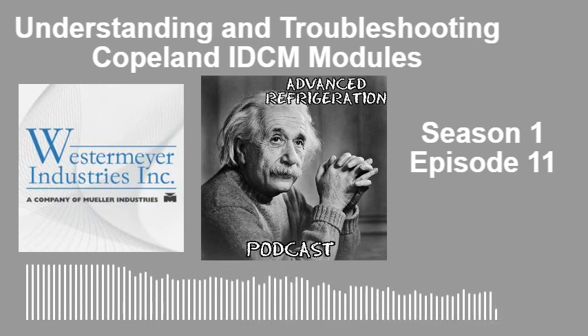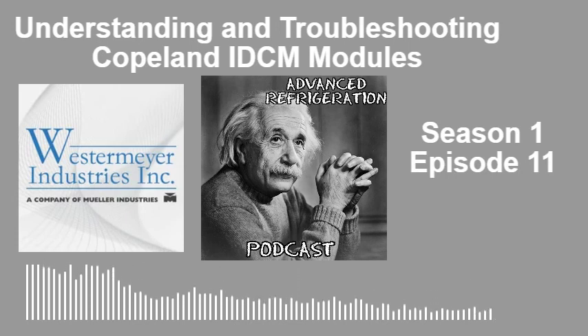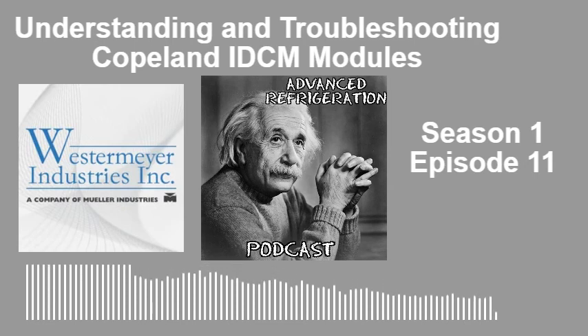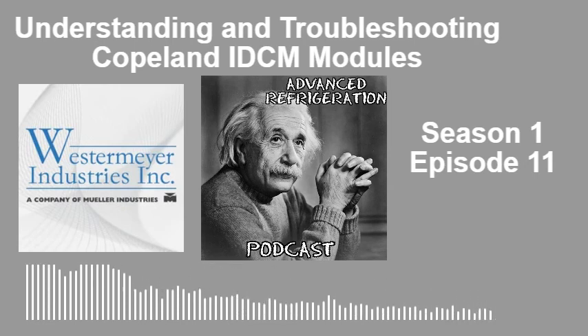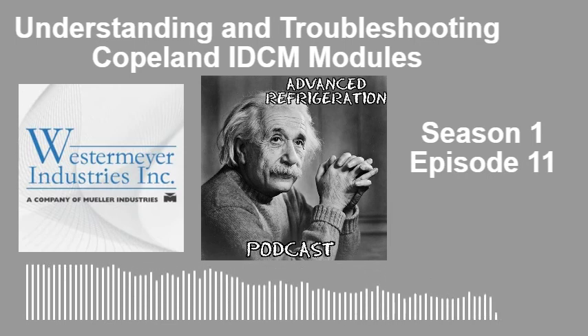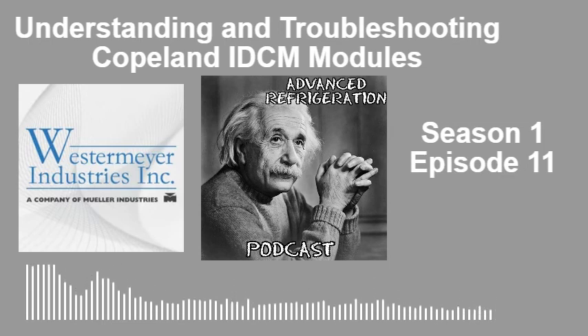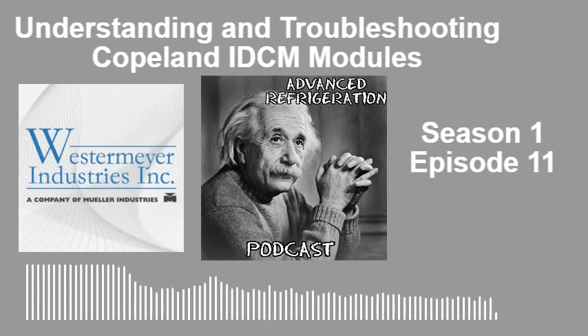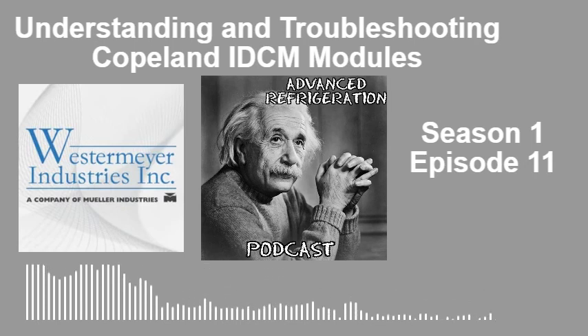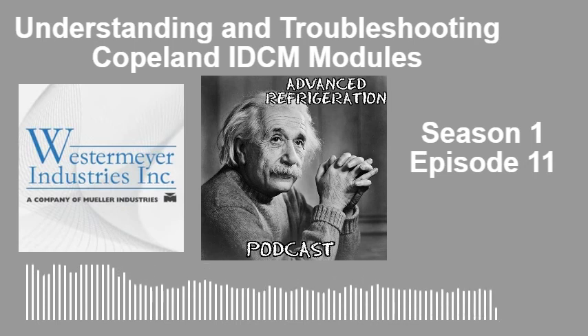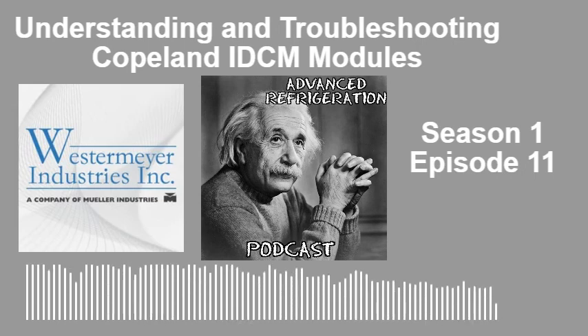That's a good overview. So what we're going to go over tonight is off of the Emerson bulletin, AE Bulletin 1328, which is the IDCM controller bulletin. Everything we're going to be going over is inside that bulletin, for you guys' reference. This IDCM controller is a pulse width modulation controller that gets a signal from an EMS controller in the form of a 1 to 5 volt signal if it's a 3D or a scroll. And if it's a 4D and 6D, it's going to be a 3 to 5 volt DC signal.